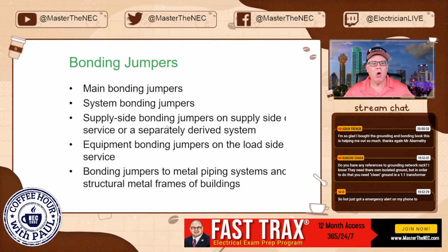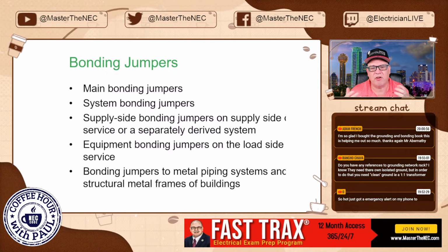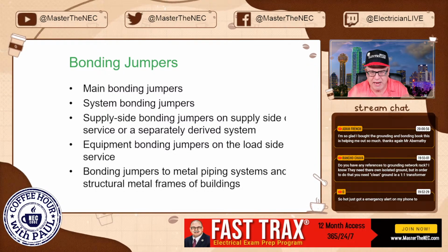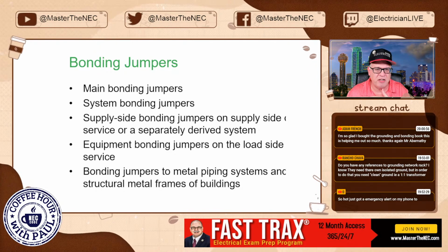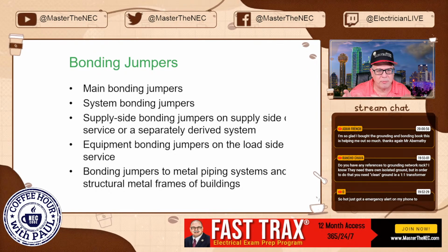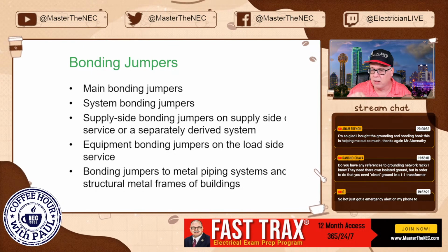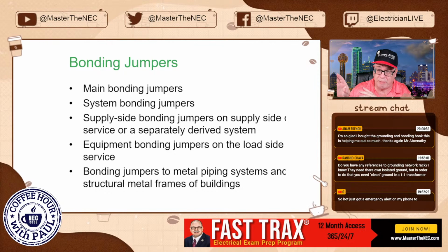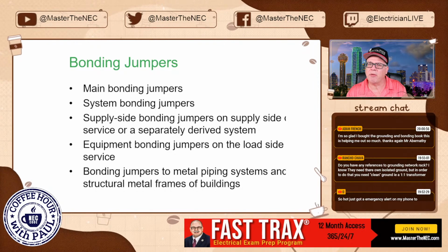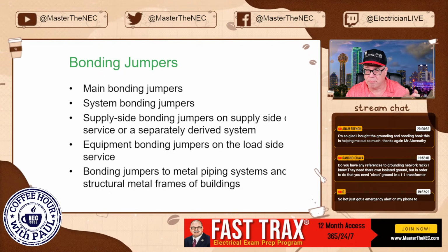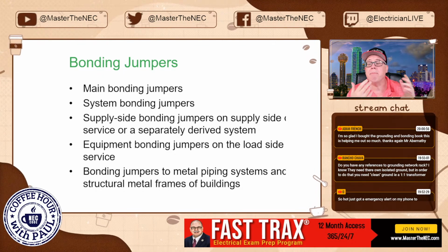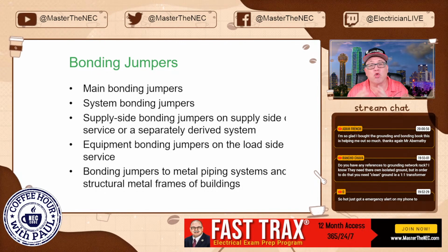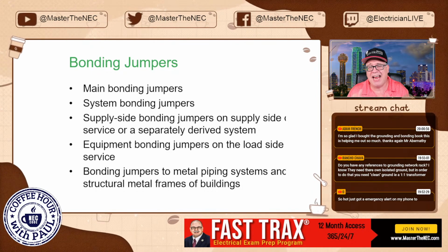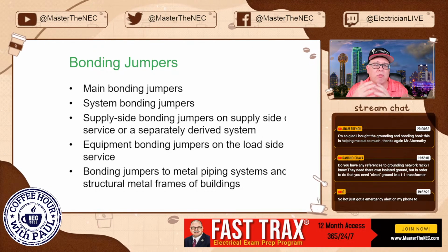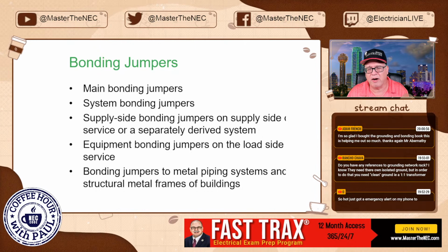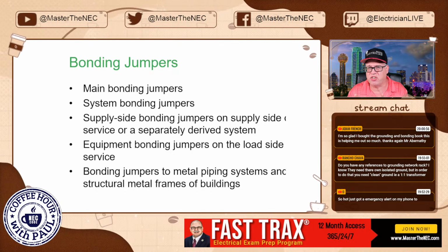All right, bonding jumpers. We have a myriad of jumpers, and we lump everything into bonding jumpers, but they have specific duties. We have main bonding jumpers, we have system bonding jumpers. Typically, you'll see system bonding jumpers on separately derived systems, like a generator, if it's truly separately derived, a transformer, which is separately derived. The main bonding jumper is what you're going to see in your main service equipment, main service switchgear, things like that. It intimately connects the grounded conductor with the equipment grounds, and it gives a location for the grounding electrode conductor to make a connection. Okay, and there are some allowances in there, and we'll cover that when we get there, but that's the general gist of it.